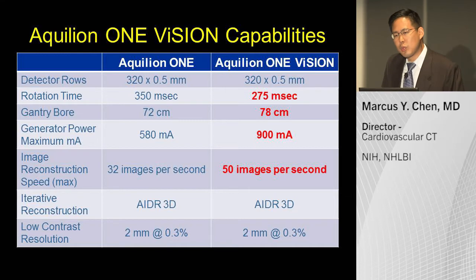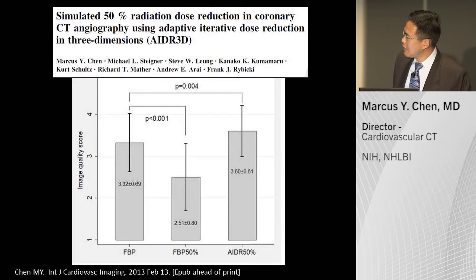With AIDR 3D iterative reconstruction, we have demonstrated that you can safely reduce the radiation exposure by 50% compared to traditional filter back projection. A standard filter back projection image at full dose versus a 50% dose reduction with filter back projection appears a bit grainy. But when you apply AIDR 3D, image quality at 50% of the radiation dose is very similar to — and actually scores slightly better than — 100% radiation dose with traditional filter back projection.